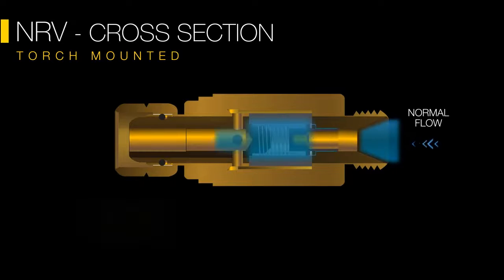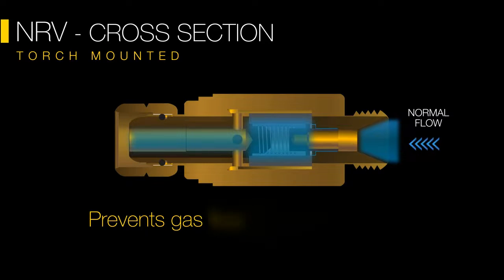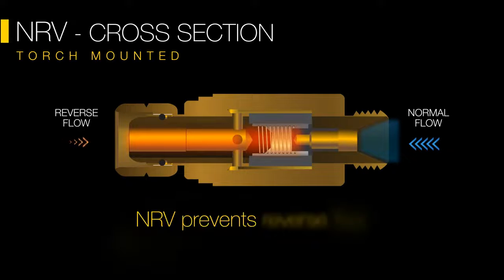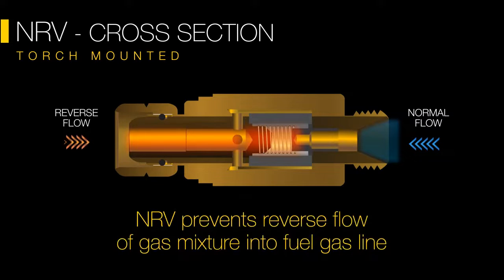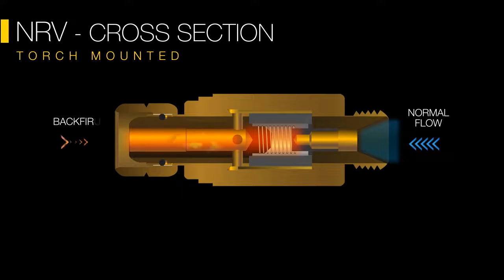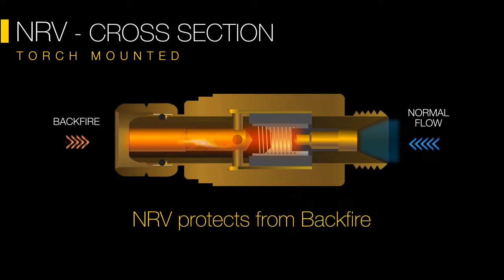The non-return valve allows gas to flow in only one direction. It shuts off gas flow in the reverse direction and prevents the reverse flow of oxygen or flame. It also acts as the first line of defense against backfire and sustained backfire.